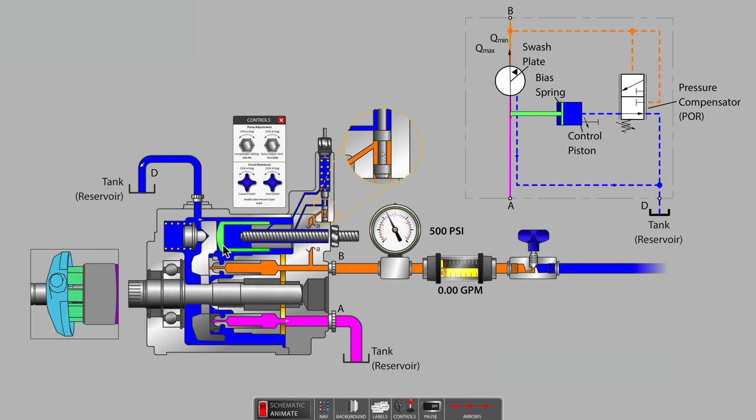The resizing of the pump is accomplished by taking pump outlet fluid and using it to extend the control piston. When the swashplate moves towards the vertical position, the individual pumping pistons in the cylinder barrel now have a near zero stroke length. The pump is maintaining 500 psi maximum system pressure on the outlet line.